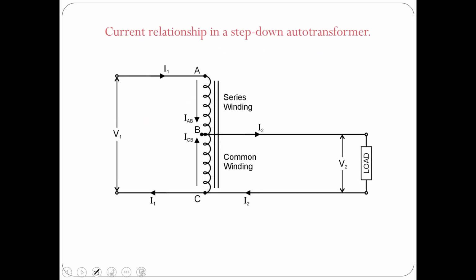Okay, looking at the current relationship. What happens with this is, well, the number one rule still applies for transformers. Whatever the volt-amp output is going to be, that is the volt-amp input. Okay, and so we're going to use that concept when we're looking at this. We're going to calculate the VA of the load, and we know that that's going to be the VA coming in.